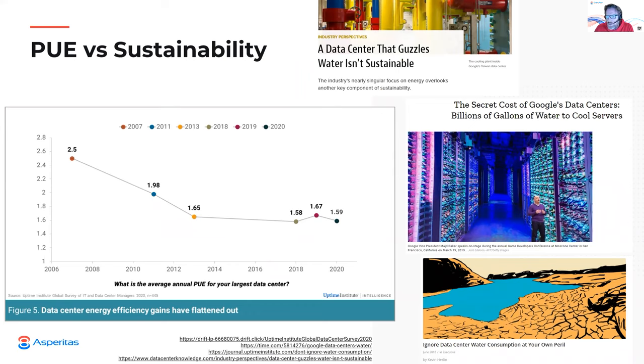According to the Uptime Institute, PUE has flatlined over the past 6 years. PUE has served an important and fundamental goal, but from a global perspective, facilities are no longer inefficient when looking at PUE alone. The very low PUE values around the Arctic Circle, for example, are offset by the industry growth in tropical areas where a PUE of 2.0 can still be considered very efficient. In fact, the measures taken to achieve the efficiency of data centers are now becoming a new focus for sustainability. And this relates to water usage due to an explosive growth of adiabatic or evaporative cooling. The evaporative element being the obvious culprit.